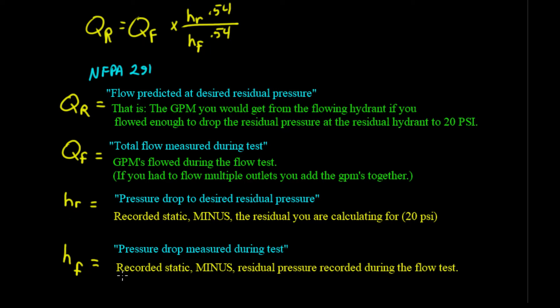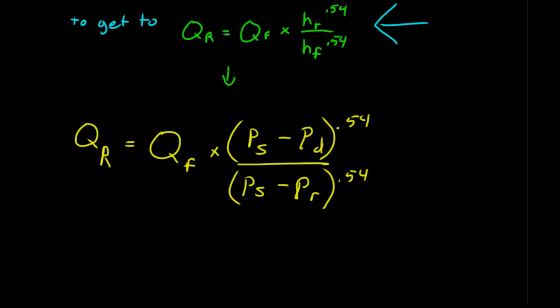HF, pressure drop measured during test. That's your recorded static minus your residual pressure recorded during the flow test. So, the way they get that is from this.